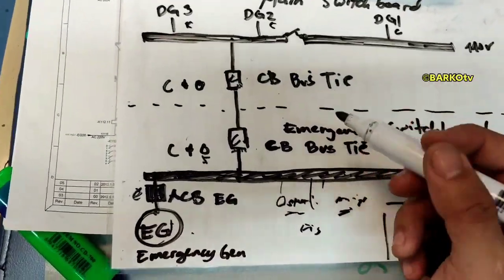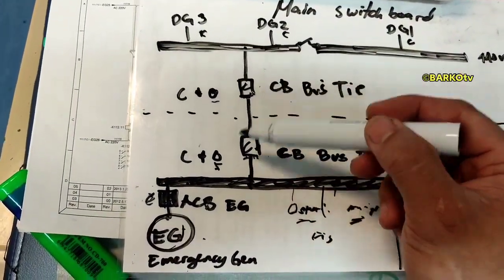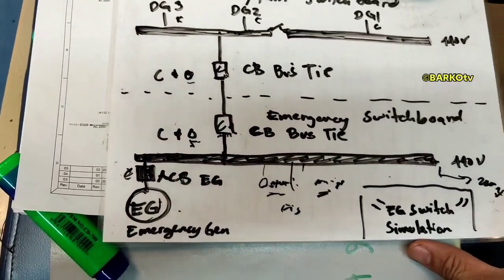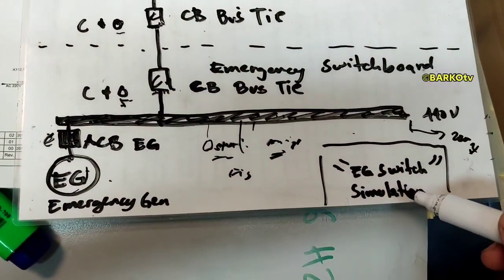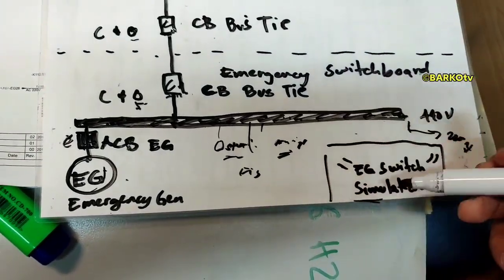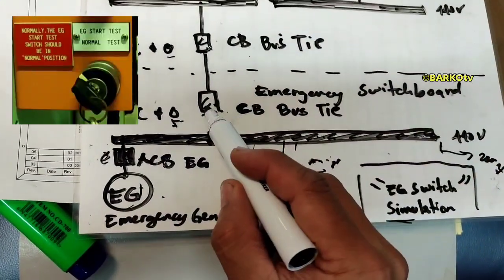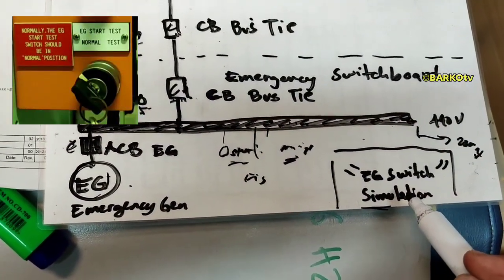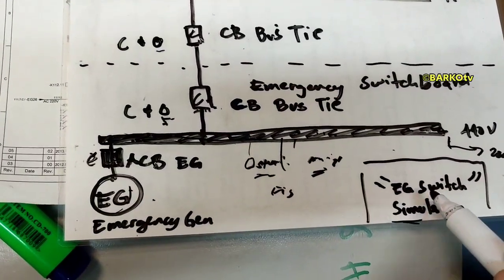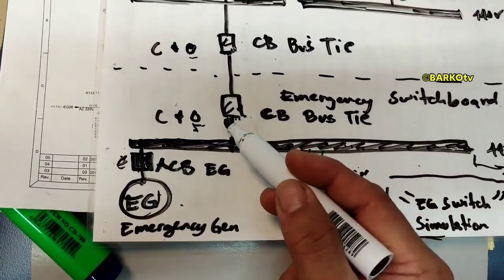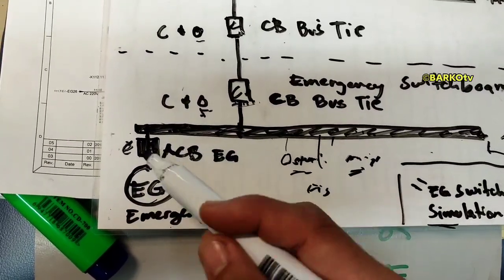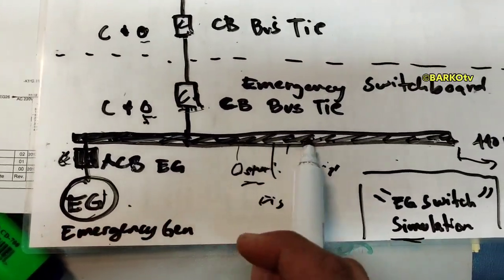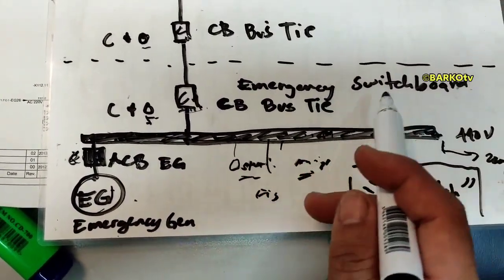The third scenario is using the simulation switch. When you turn the simulation switch to test, it commands the bus tie breaker located at the emergency switchboard to open. The simulation switch commands that breaker to open. After that, the emergency generator automatically starts, and after the delay the ACB closes and supplies the emergency switchboard.